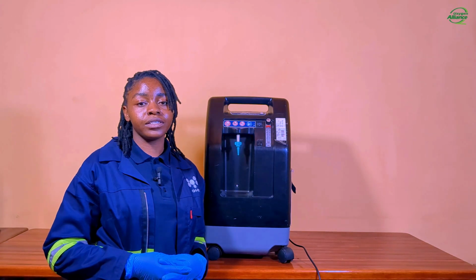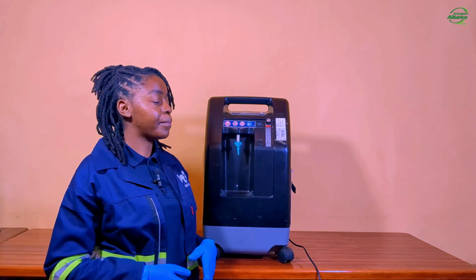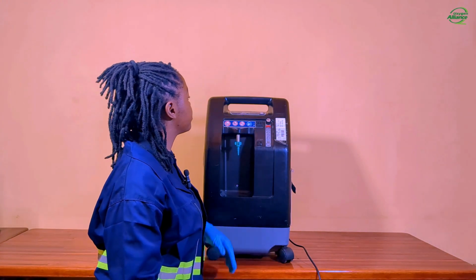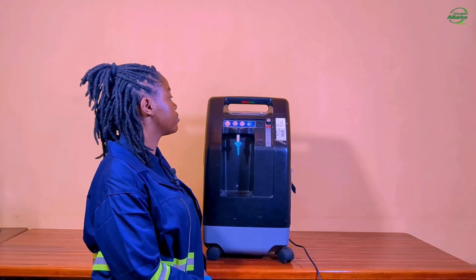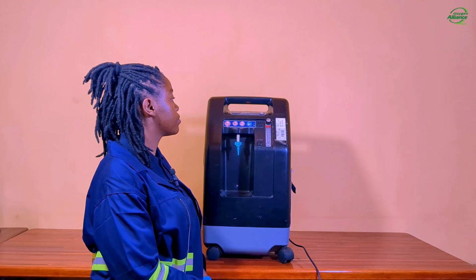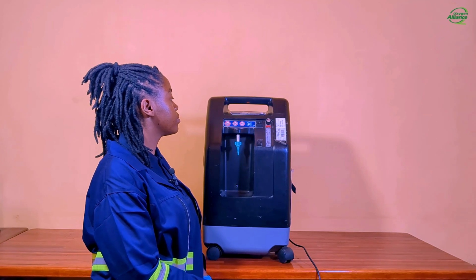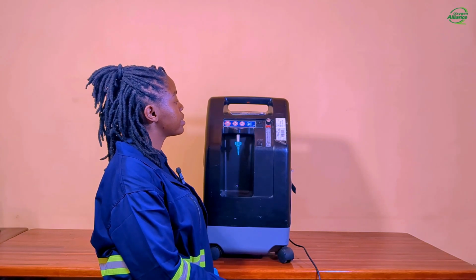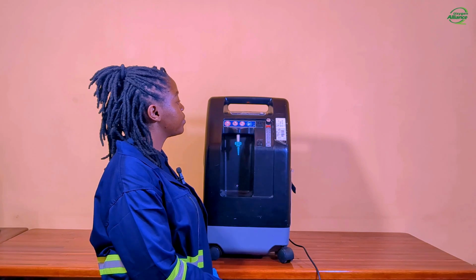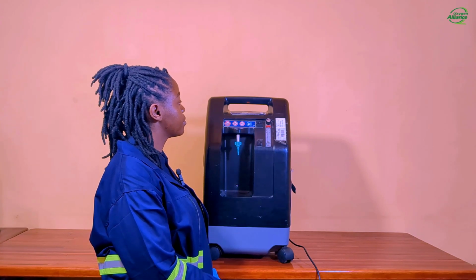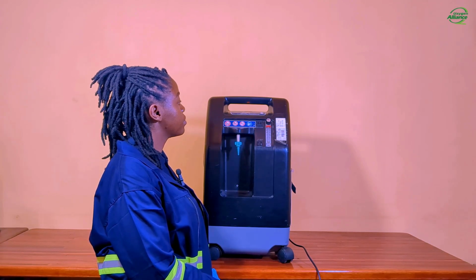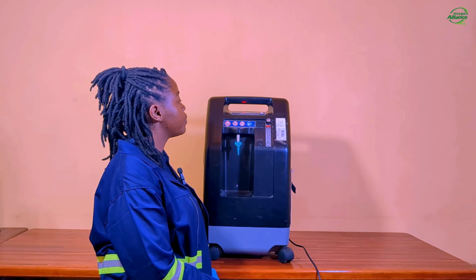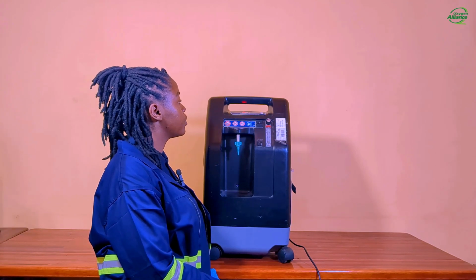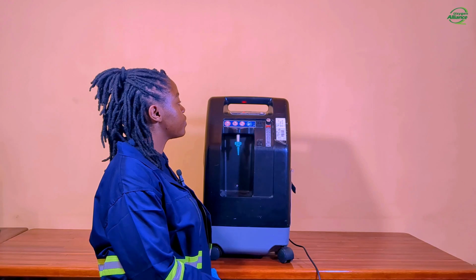I will now turn on the concentrator to demonstrate this alarm. So you will notice that the compressor is off. And after a few seconds, the service indicator light will turn on, indicating compressor failure.